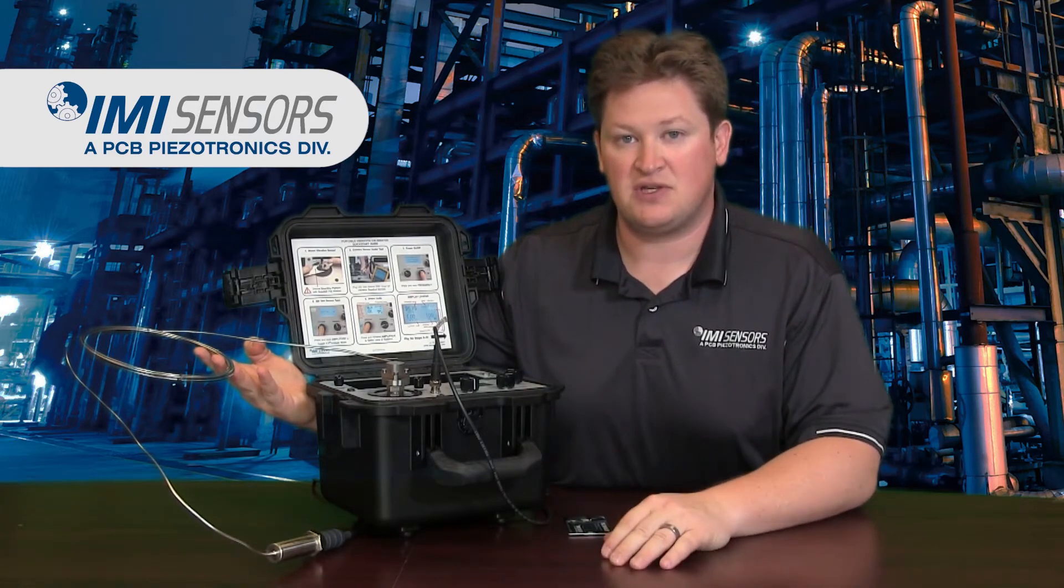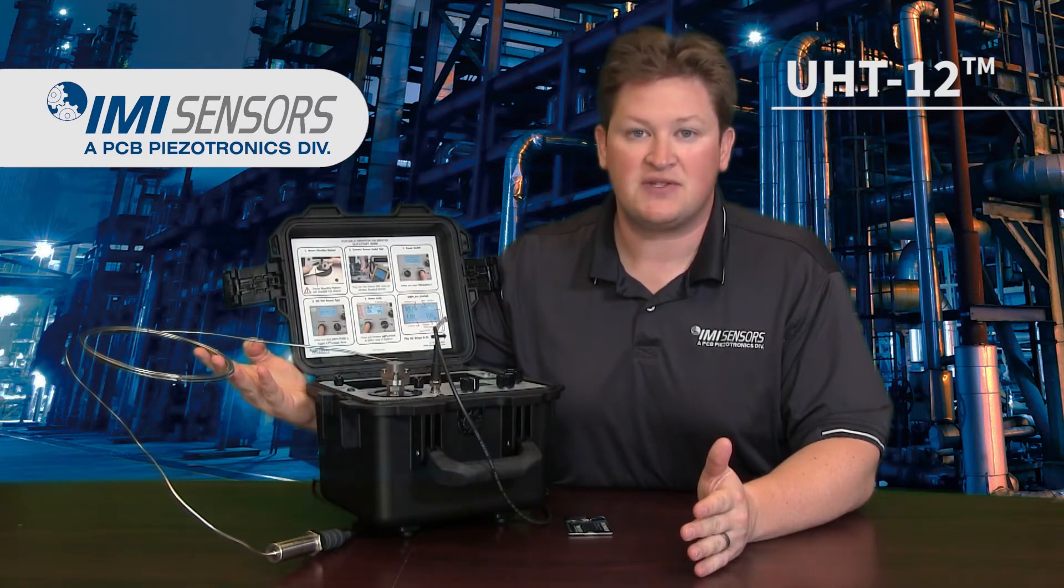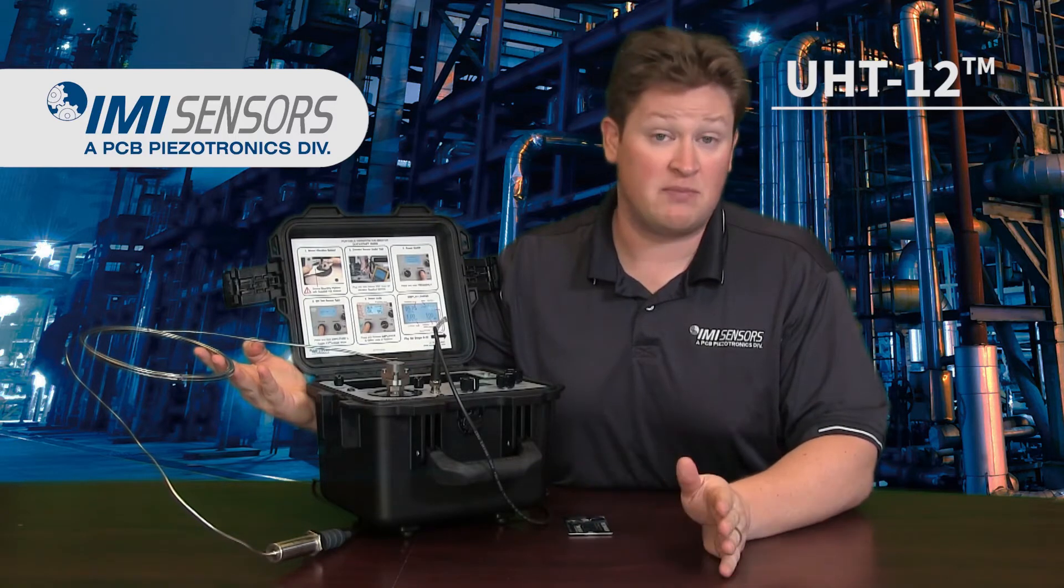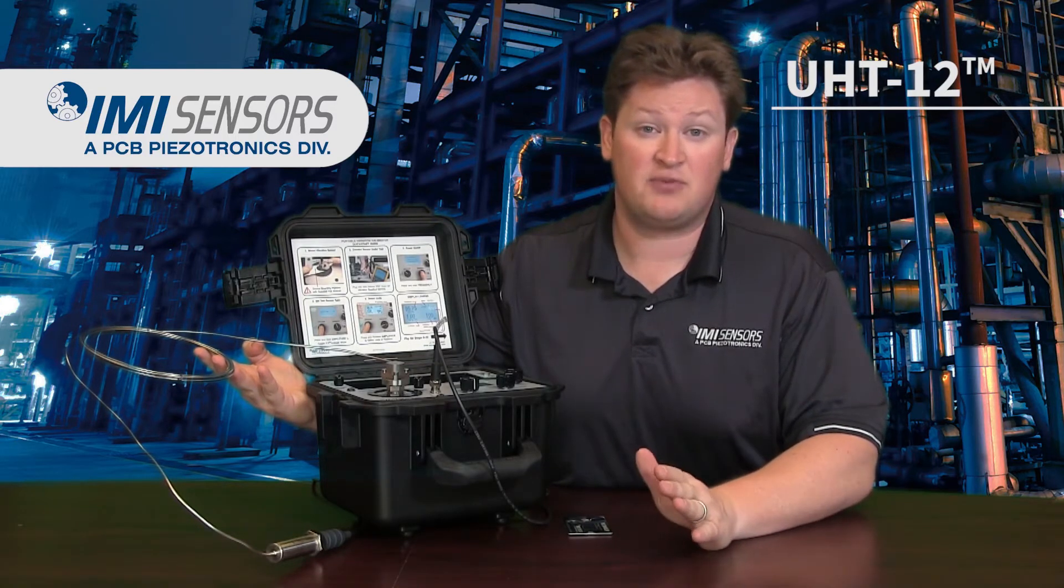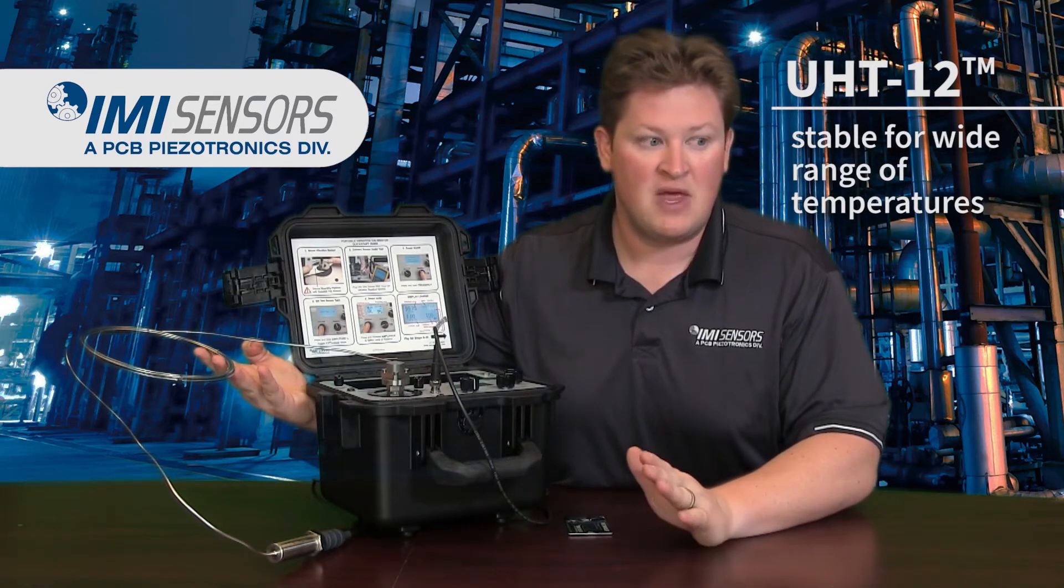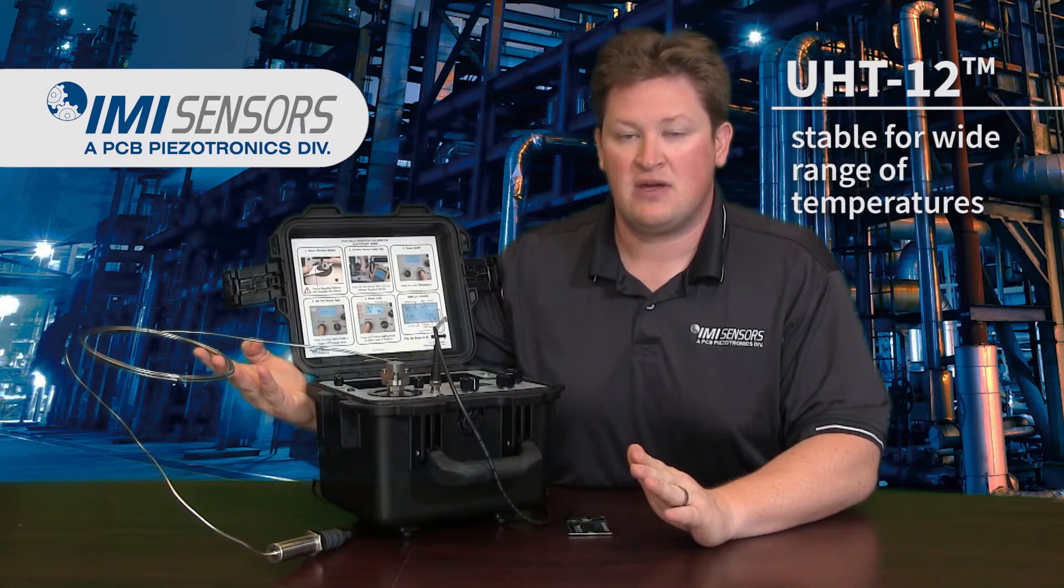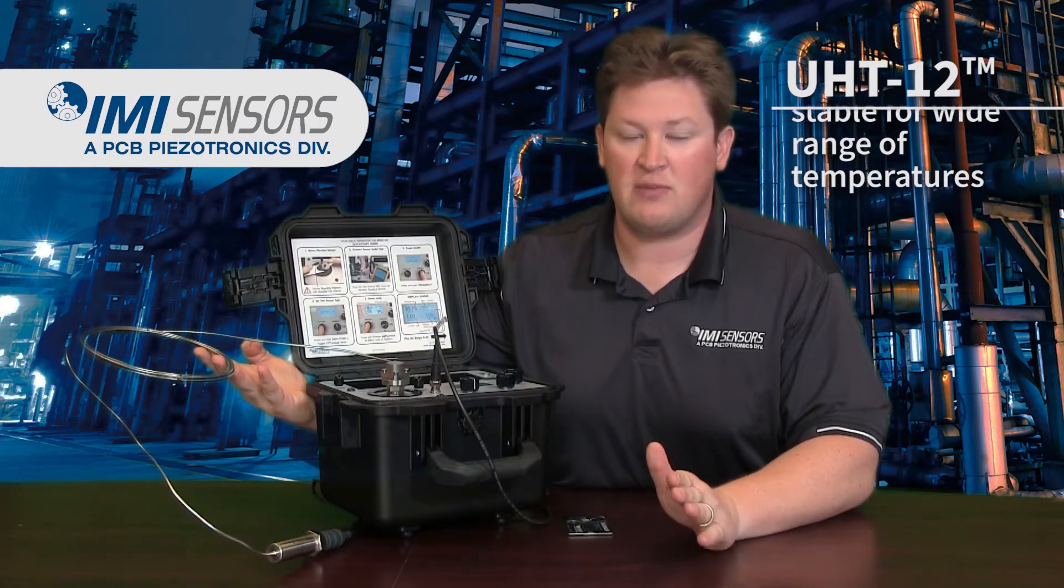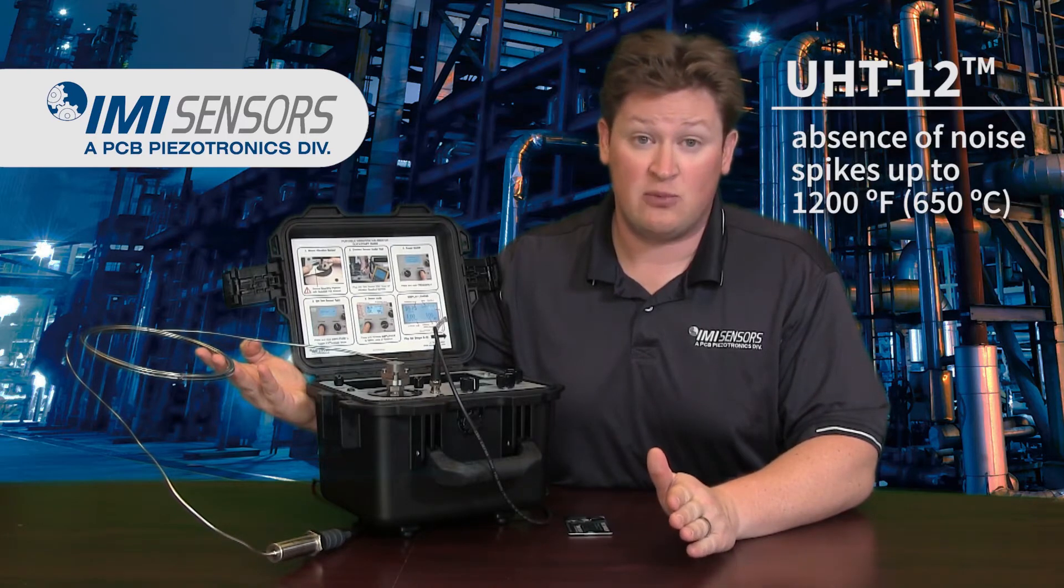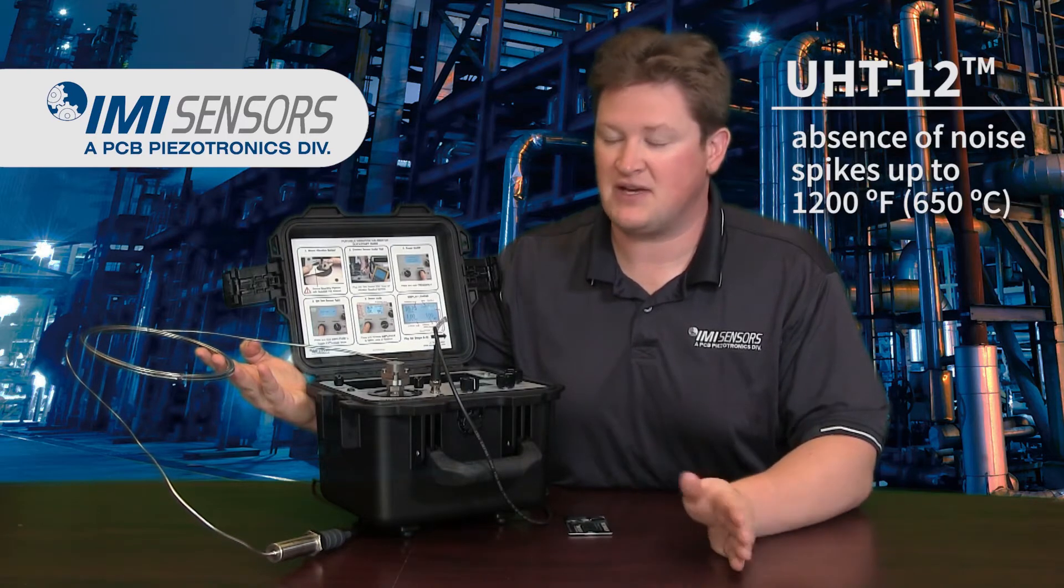It's part of IMI Sensors UHT12, PCB Piezotronics UHT12 sensor design, which offers versus competitive models superior temperature stability over a wide frequency range. They also offer terrific performance with the absence of pyroelectric noise spikes, which can occur from time to time. Many technicians are very familiar with pyroelectric noise spikes on these transducers.